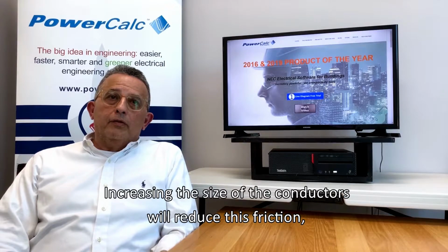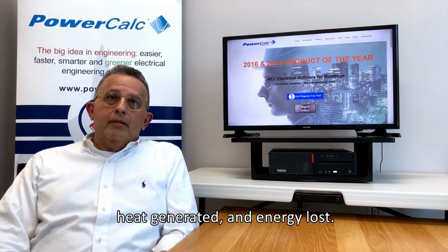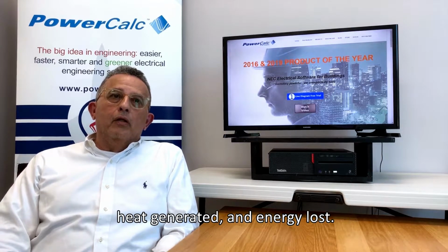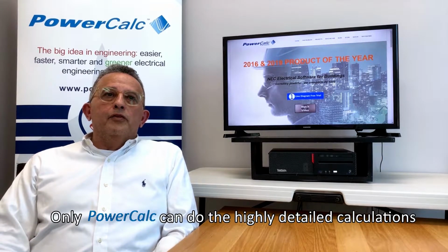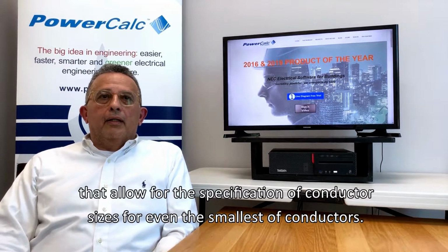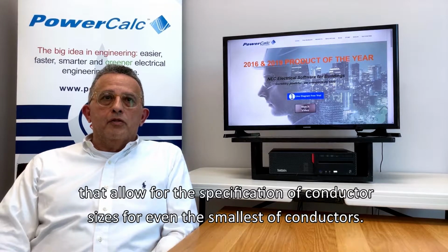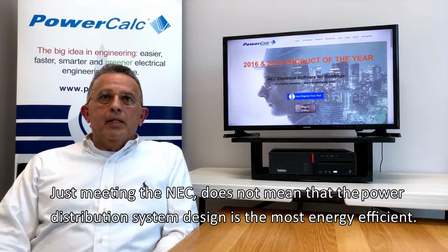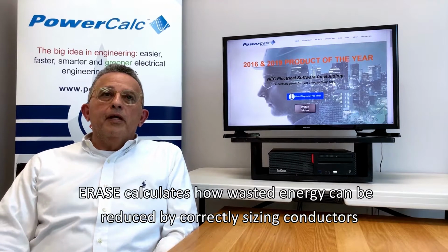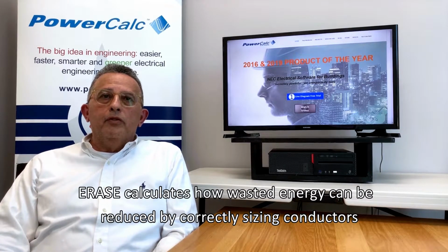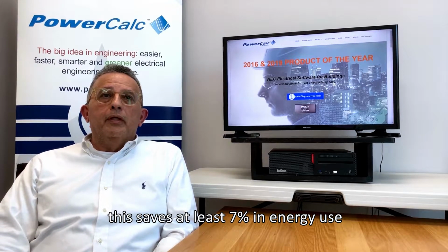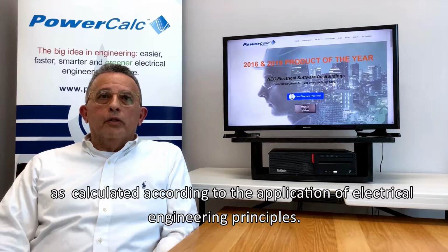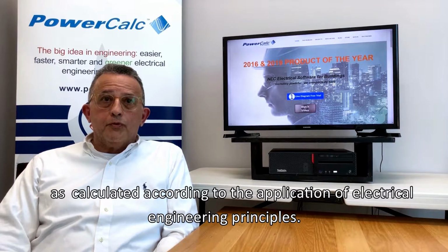Increasing the size of the conductors will reduce this friction, heat generated, and energy lost. Only PowerCalc can do the highly detailed calculations that allow specification of conductor sizes, even for the smallest conductors. Just meeting the NEC does not mean the power distribution system design is the most energy efficient. ERASE calculates how wasted energy can be reduced by correctly sizing conductors.